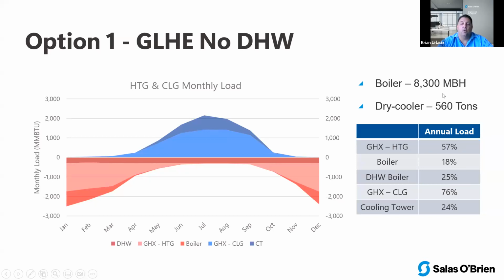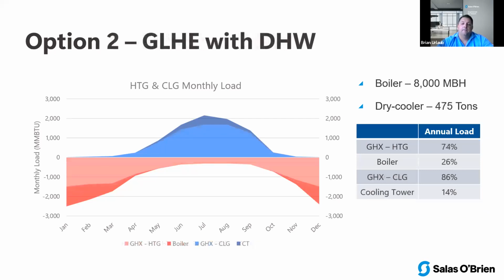And we were still needing a boiler of around 8,300 MBH for the peak, which was really difficult again to stay under that 1 megawatt from a power perspective. So then we looked at adding the domestic hot water, because if you look at the thermal profile here, it's pretty balanced. Can we help on the cooling side by adding domestic hot water and using heat pumps instead of electric boilers? So our boiler did come down slightly.